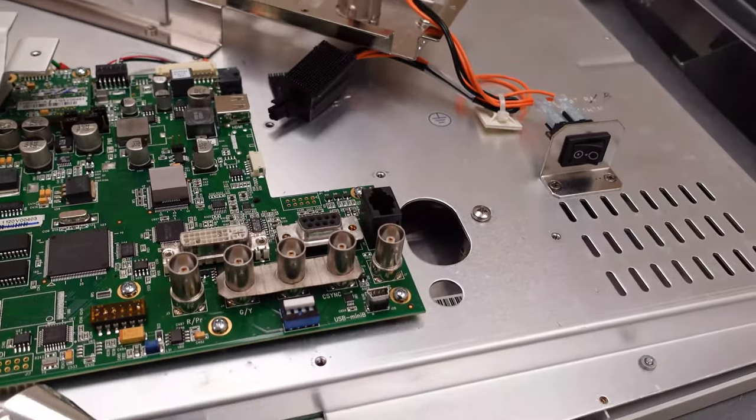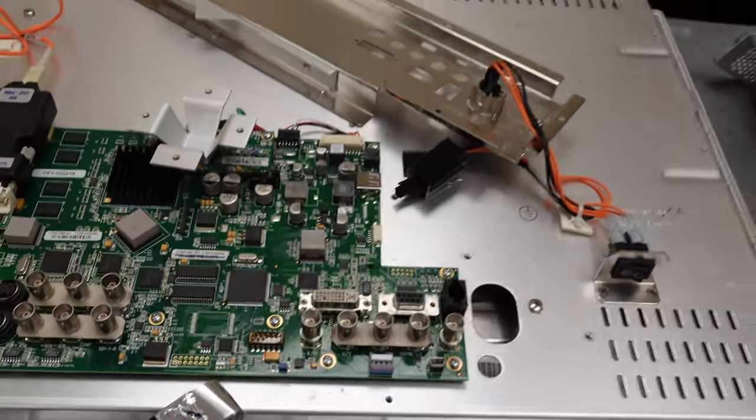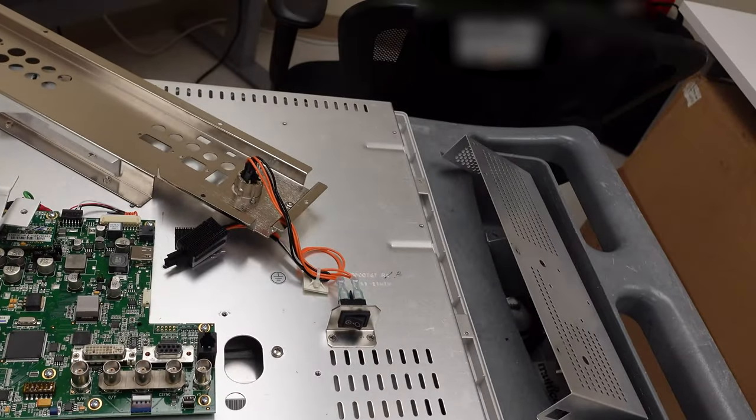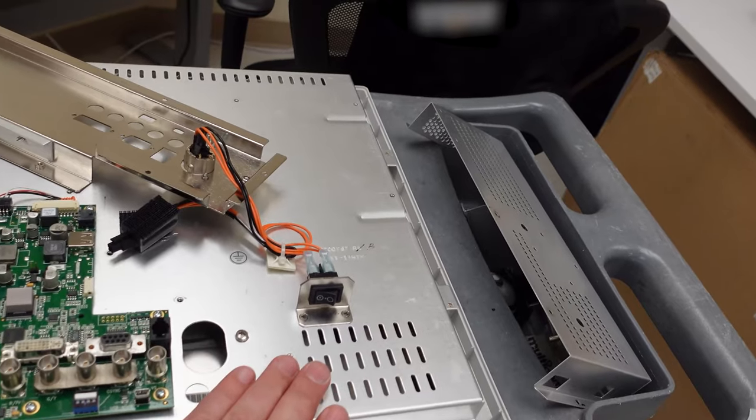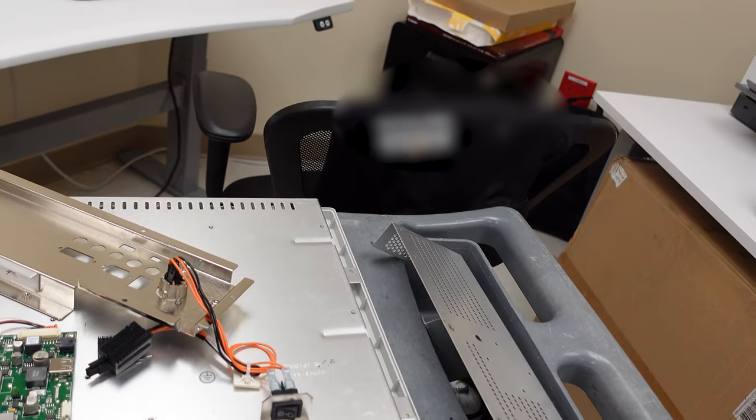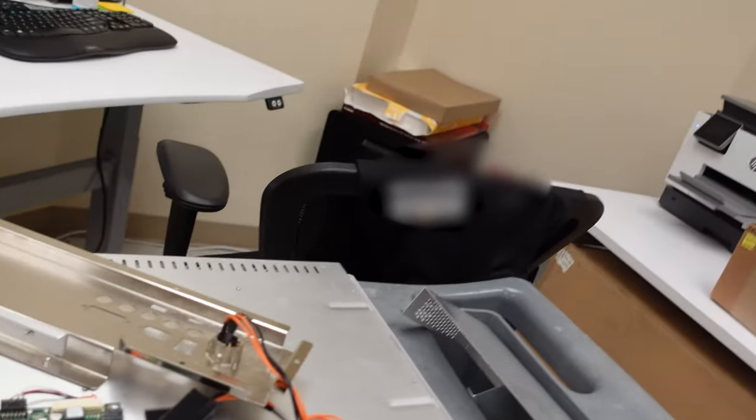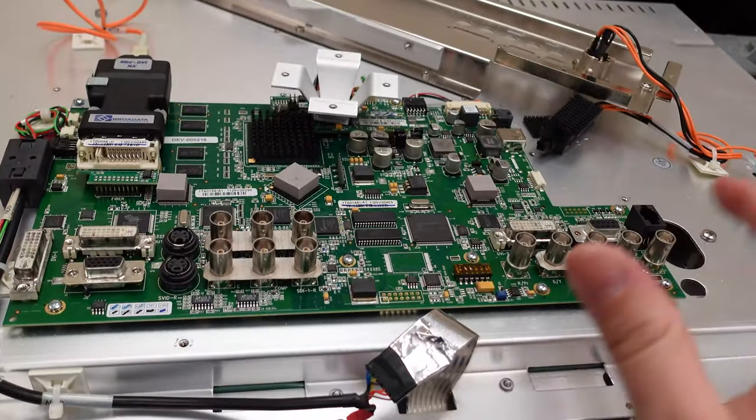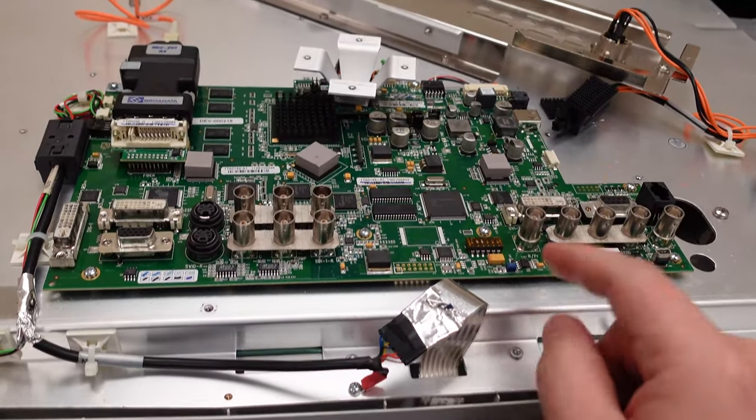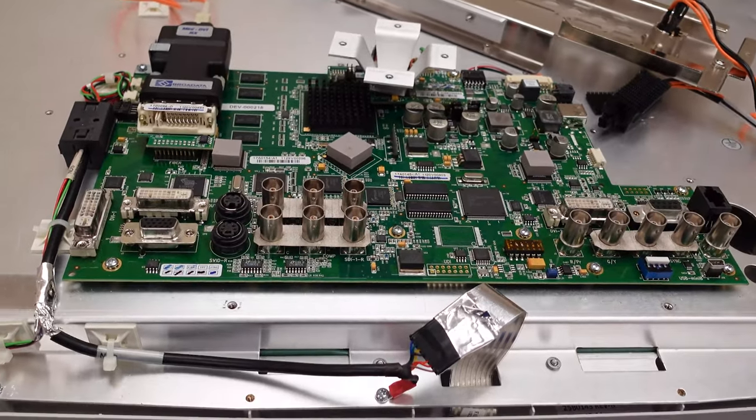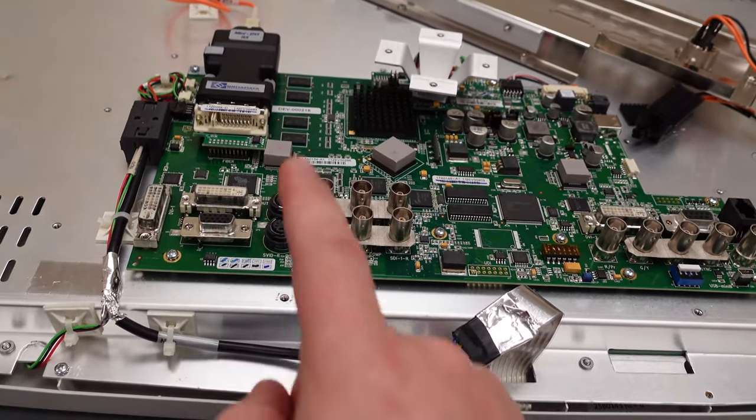That's pretty much it, guys. It's really not that complex. Don't change any jumper settings. It's been a really good display. Not very much can go wrong with it since it is LED backlit, not fluorescent backlit. These displays here are one of the most reliable displays I've actually worked with. That's the inside of a Karl Storz NDS display with the diamond LED technology. It's a good display, I really like it, and it is serviceable. You have options. Thanks for watching, guys.